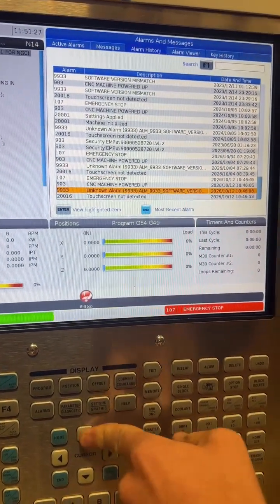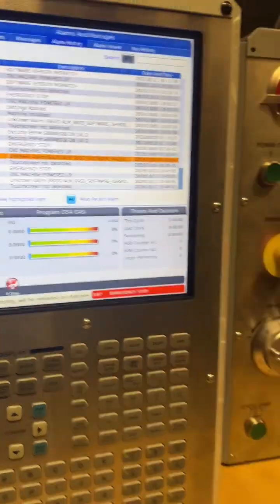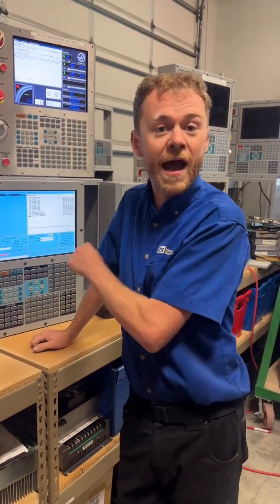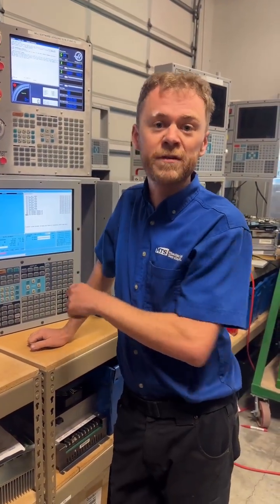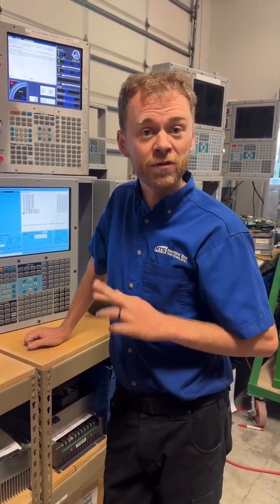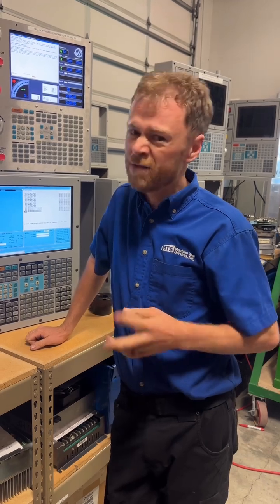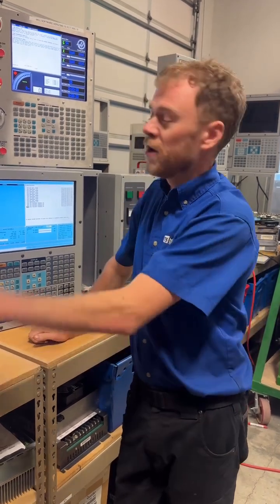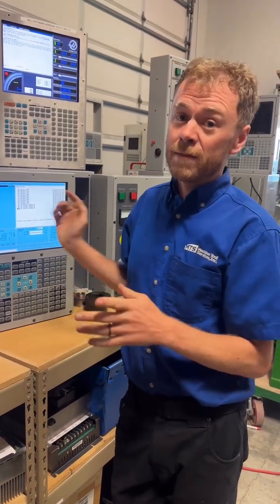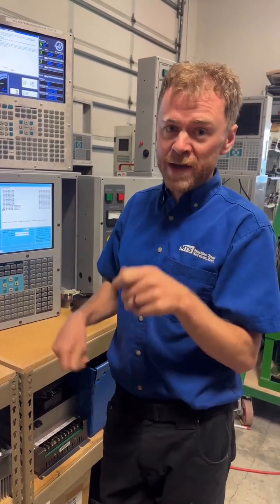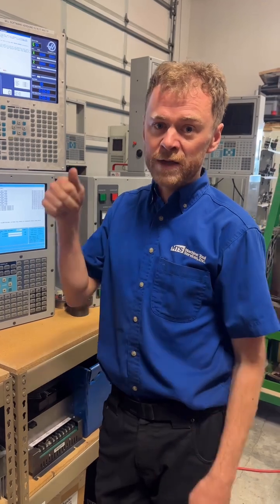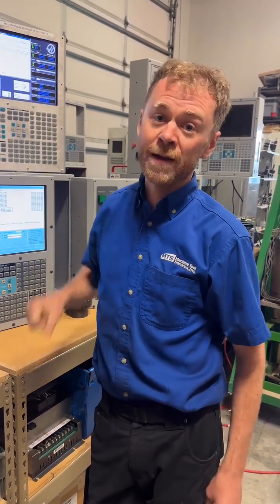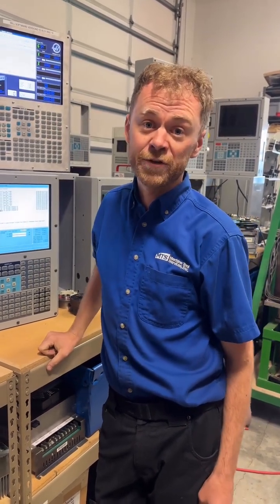Really, really helpful — say if you're troubleshooting a vector drive alarm or servo drive alarm: how often does it happen? Is it related to when it turns on and turns off, or is it only in the afternoon? Remember: alarms page, right arrow key, page up, and you can see the alarm, the date, or parameters that have changed.